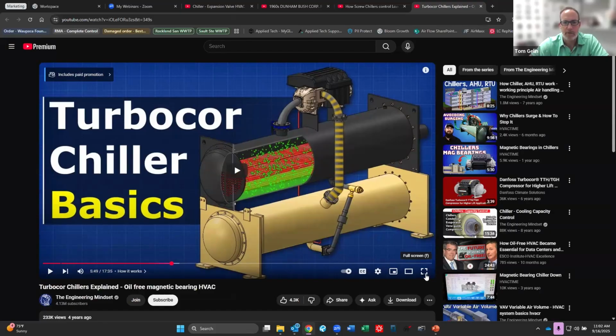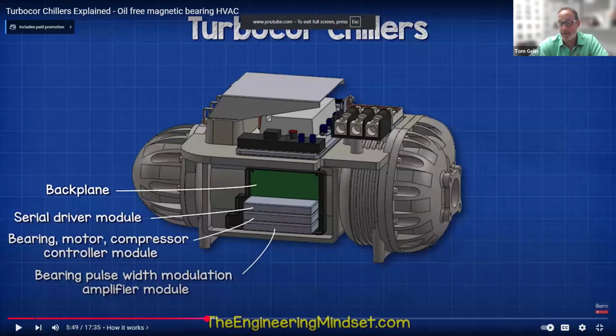There are a couple of things in here that remind me. One is that we've got a centrifugal, basically a centrifugal gas mover, not so different from a fan. So part of this is talking about the inlet vanes that go on the compressor. And the other part of it shows this permanent magnet structure, which is not much different than these EC motors that we're putting together, which have permanent magnets in them as well. Whether it's an EC as a single phase or a three-phase permanent magnet, it's the same kind of concepts, just increasing efficiency. So let's play this and get everybody up to speed. It's interesting.